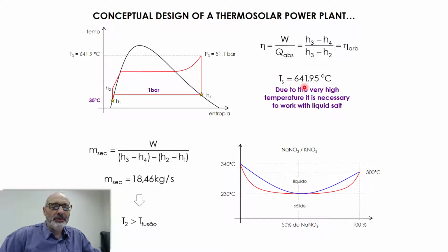An important point related to this result is that it's very high. Due to the very high temperature, it's necessary to work with liquid salt. You cannot work with vegetable oil, of course not, but mineral oils also have problems at this temperature. So we're going to use liquid salt. Let's see the possibilities. I'm not showing you all the possibilities, I'm showing you the best solution for our case, which is this mixture of salts here.